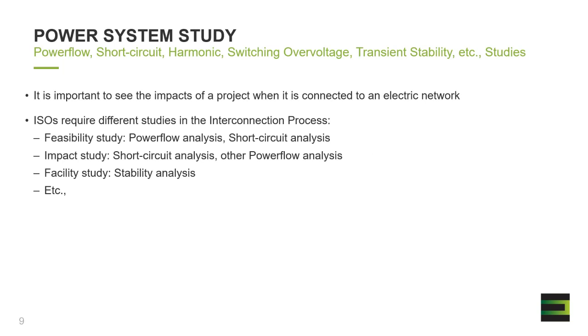There is another set of studies that is done by the interconnection customer, mainly power flow, short circuit, harmonic, transient stability, and switching overvoltage, to name a few. The motivation behind performing the second set of studies, the behind the fence studies, is to ensure that the project and the design meet the different IEEE criteria. These are required by different financing authorities to ensure that the projects being financed do not have any underlying issues which may hinder the long-term operation of the plant.